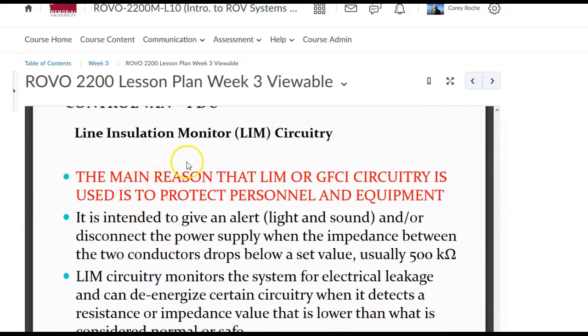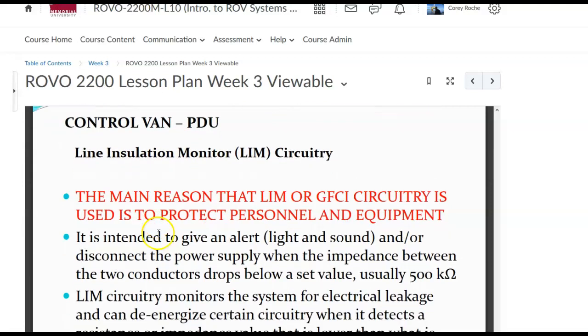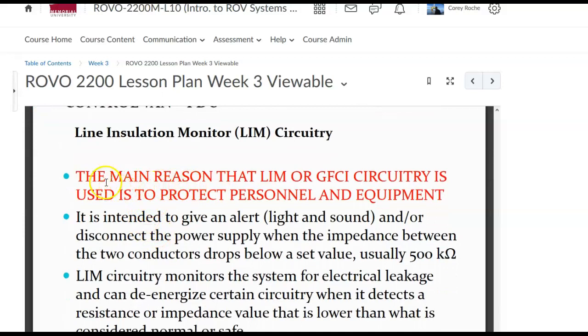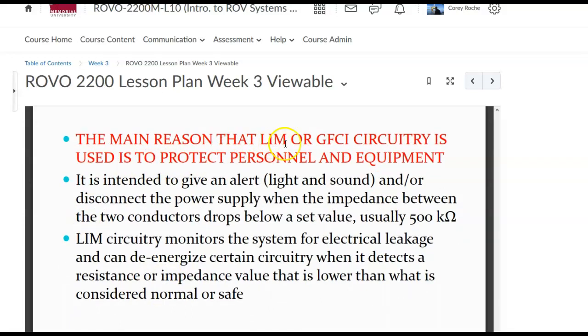So now we've got the LIM circuitry, line insulation monitors. Note this red one here, very tricky multiple choice, might be coming at you one of these days. The main reason that LIM or ground fault circuit interrupter circuitry is used is to protect personnel and equipment. It is intended to give an alert, light and sound, and/or disconnect the power supply when the impedance between the two conductors drops below a set value, usually 500 kilo ohms, right? 500,000 ohms. LIM circuitry monitors the system for electrical leakage and can de-energize certain circuitry when it detects a resistance or impedance value that is lower than what is considered normal or safe.